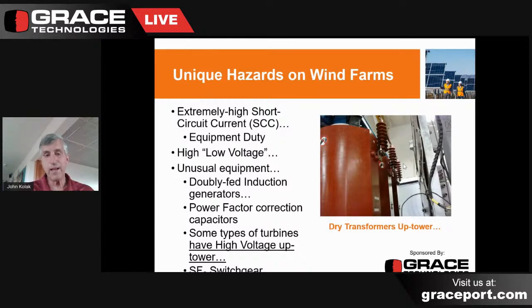And then in some cases, and what you see in the picture on the right is an example of this, some turbines are configured where they actually have 34,500 volt transformers up tower. I don't like that very much, but it's a unique situation you'd find on a wind farm, where you have high voltage windings, 34,500 volt windings up tower in the nacelle itself. And that requires specific training on grounding and lockout tagout.